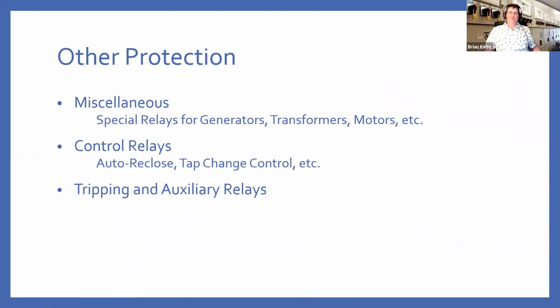There are various other special protection devices, generators, motors, transformers, etc. But they tend to be bespoke to the device that you're protecting. Similarly, you will have auto reclosers and tap changers that are there to control things like auto voltage control for your distribution network. And you have a number of auxiliary devices that are there to interface with the other equipment on the network.